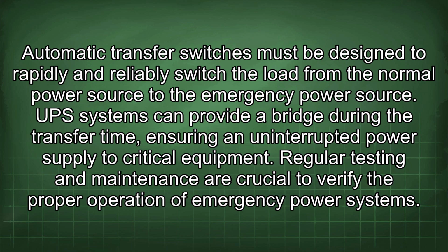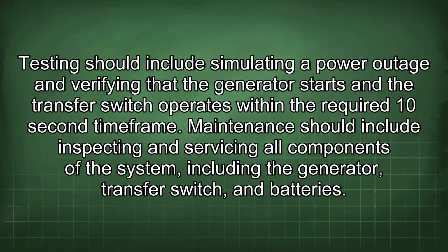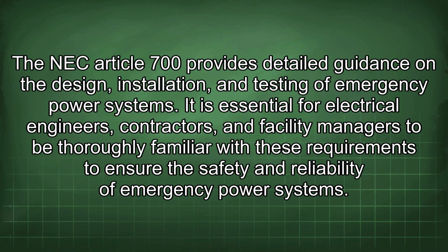Regular testing and maintenance are crucial to verify the proper operation of emergency power systems. Testing should include simulating a power outage and verifying that the generator starts and the transfer switch operates within the required 10-second time frame. Maintenance should include inspecting and servicing all components of the system, including the generator, transfer switch, and batteries. The NEC Article 700 provides detailed guidance on the design, installation, and testing of emergency power systems.